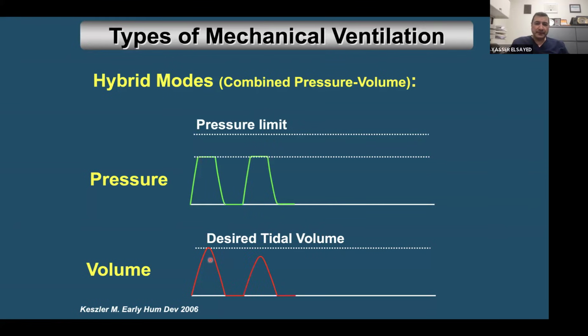Assume that the tidal volume became less than the preset. So how does the machine detect that? Through the expiratory limb, there is a flow sensor that can detect and estimate the expired tidal volume and can synchronize that with the machine to ask the machine for the next breath, please increase the pressure because the tidal volume now is less. So increase the pressure so the next breath will reach the preset, which is 5 again instead of 4. So now you have higher pressure needed because the compliance decreased.